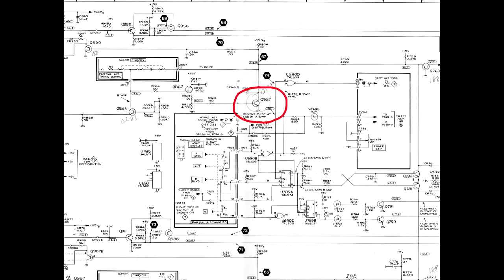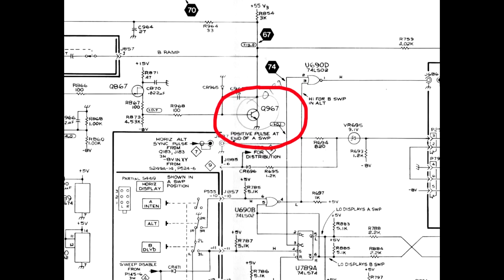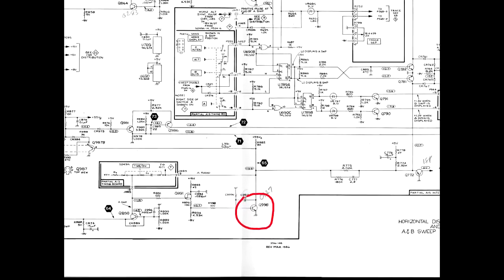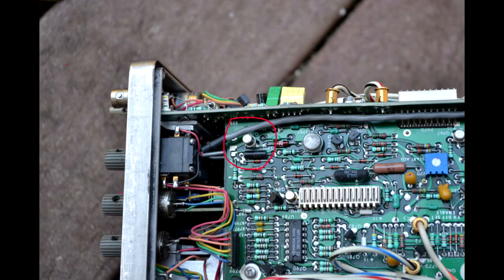There are two transistors which cause failures in the A and B sweep designated Q967 and Q998 in the 468 and Q4570 and 4598 in the 465B. Even in instruments with most of the transistors soldered in, these are socketed which suggests a failure problem with these was anticipated.